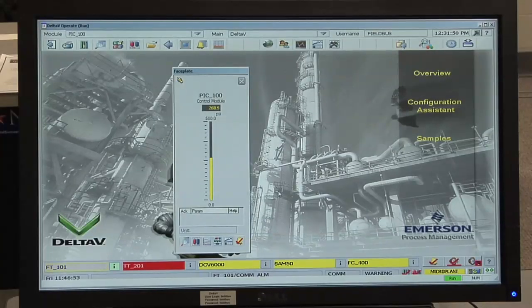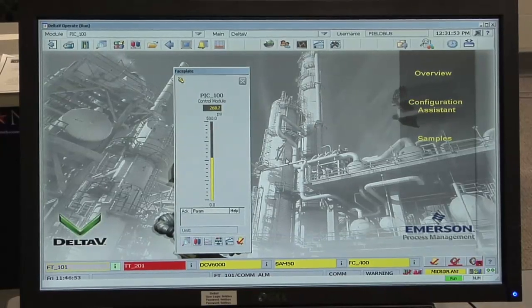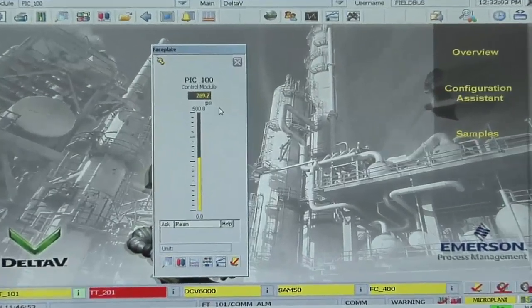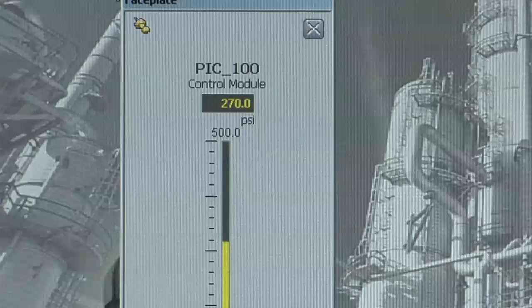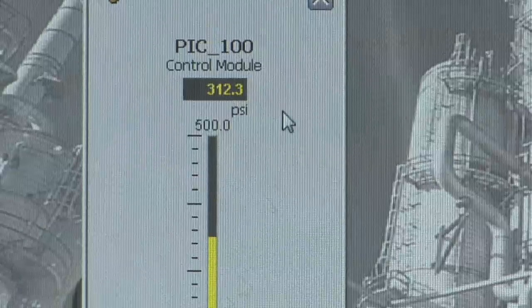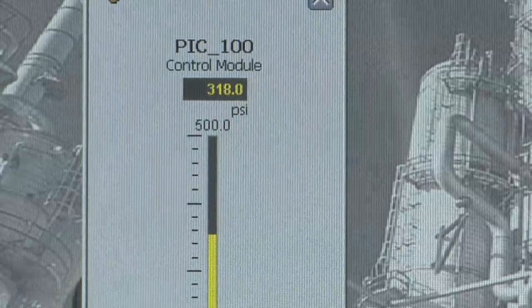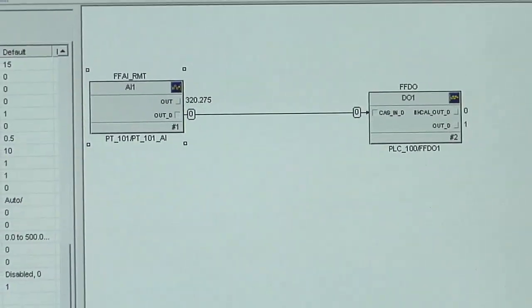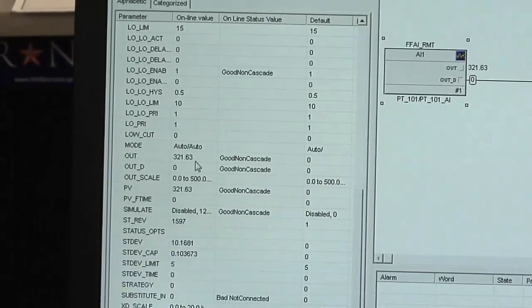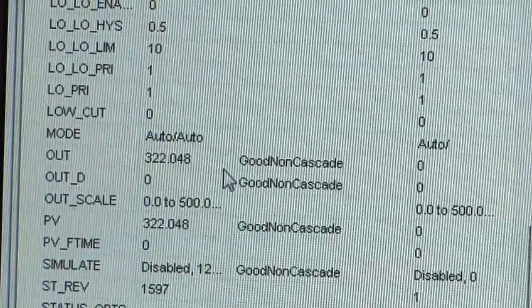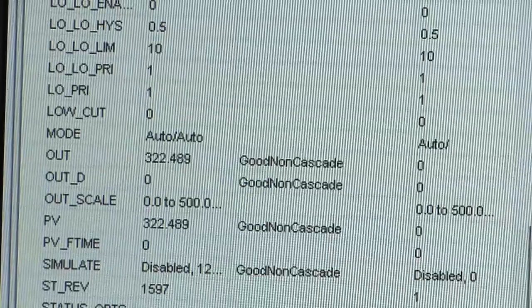I'm looking at the psi measurement coming out of our pressure transmitter right now, and currently we are in a good range, about 269 psi. We're going to show how it's going to present as that pressure exceeds our scale. Going to Control Studio — you can see the value we're putting out right now at 321 psi — and we'll have Chuck actually crank that pressure up, and we'll see what happens as that pressure changes.